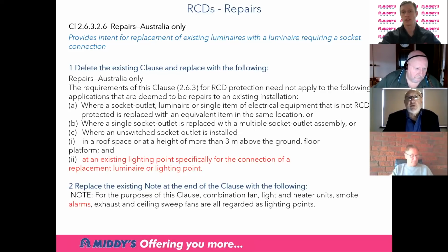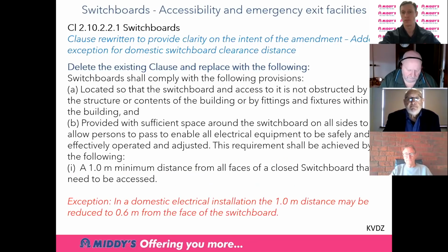So if you've got a lighting point and you actually have to put a socket outlet in the ceiling to plug in that lighting point, or it may be also an exhaust fan or the like, you don't have to go back to the RCD, to the switchboard and add an RCD. And again, we've had to change that smoke alarms terminology from smoke detectors. So we can move on from that.